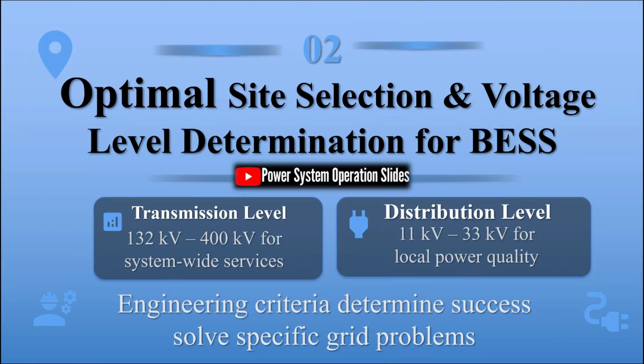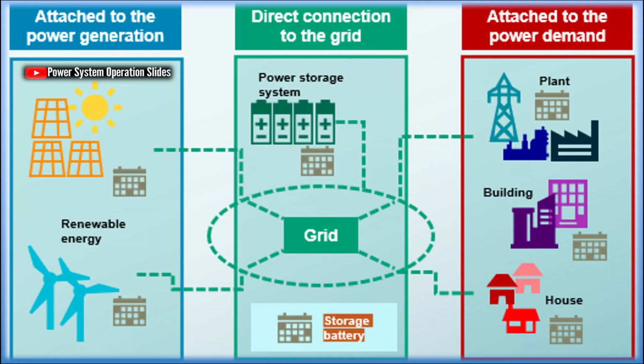These services include frequency regulation, which requires rapid response capabilities to maintain system frequency at 50 or 60 Hz, congestion relief, which involves storing energy during periods of transmission constraint and discharging it when constraints are relaxed, renewable firming, which smooths the variable output of wind and solar resources to make them more dispatchable, and inter-area oscillation damping, which involves injecting or absorbing power to dampen electromechanical oscillations that can threaten system stability.